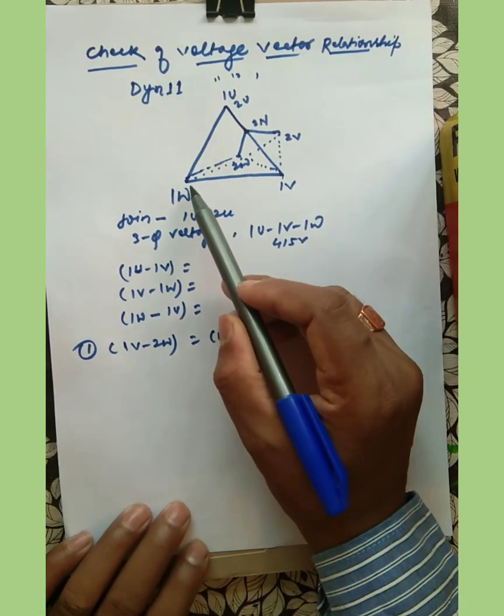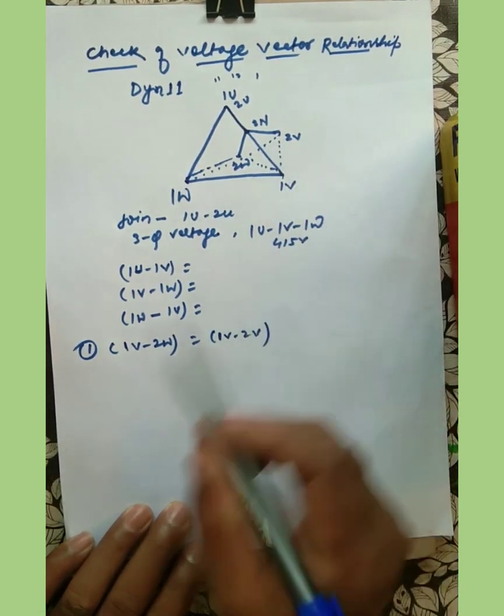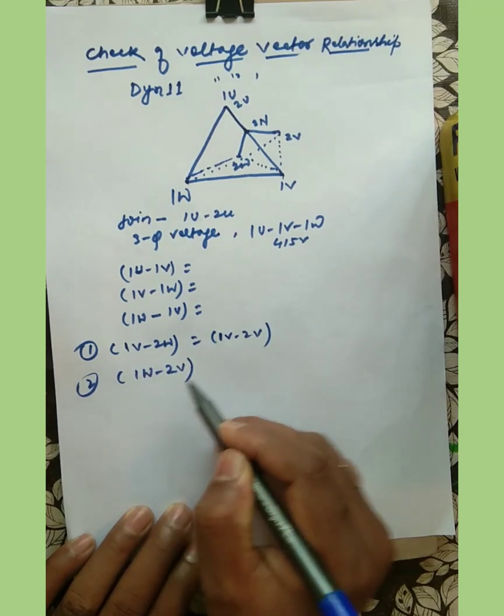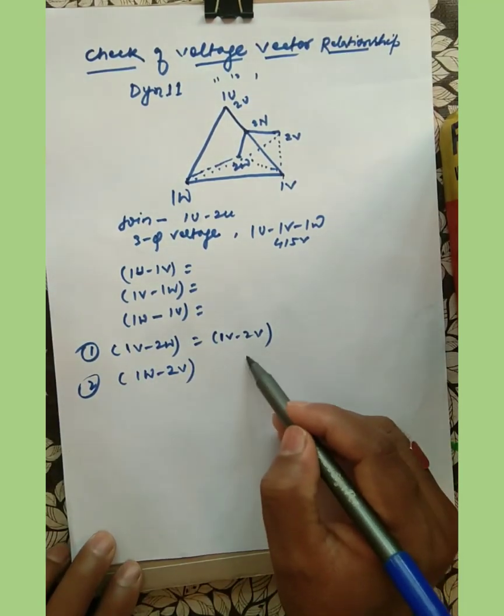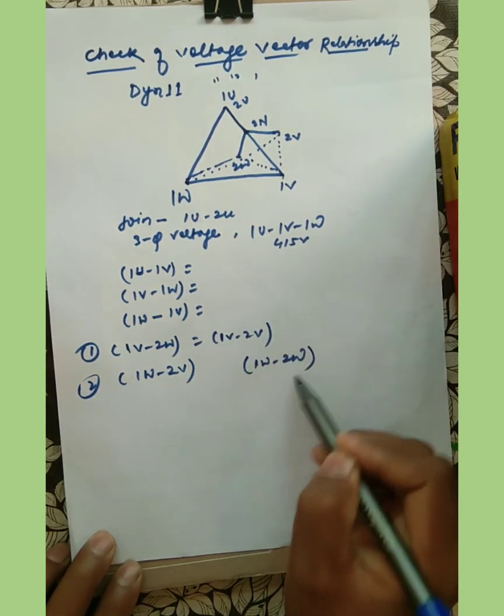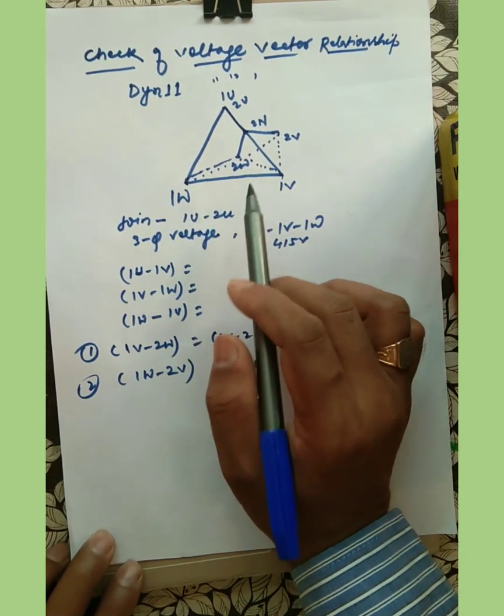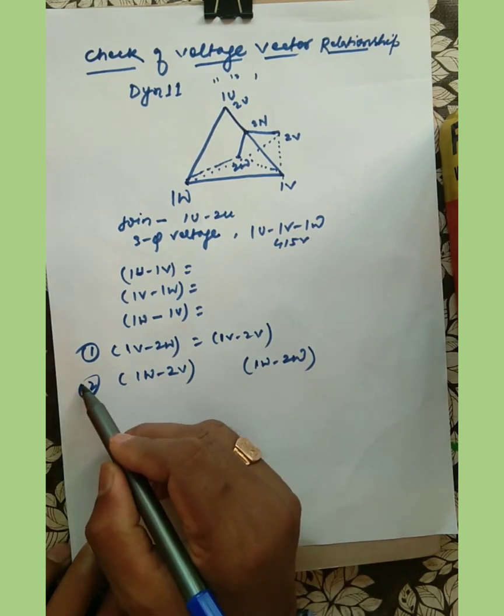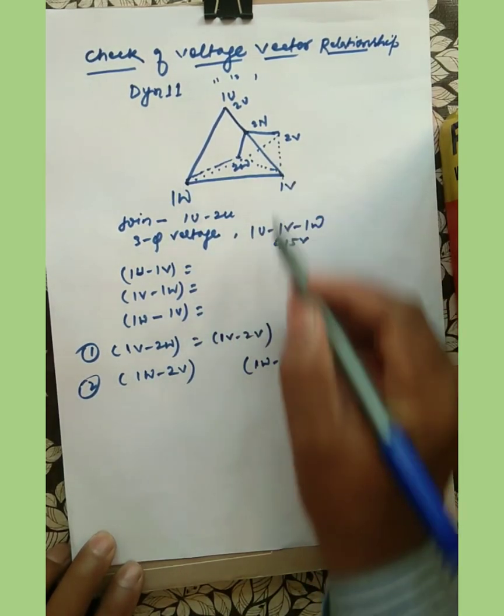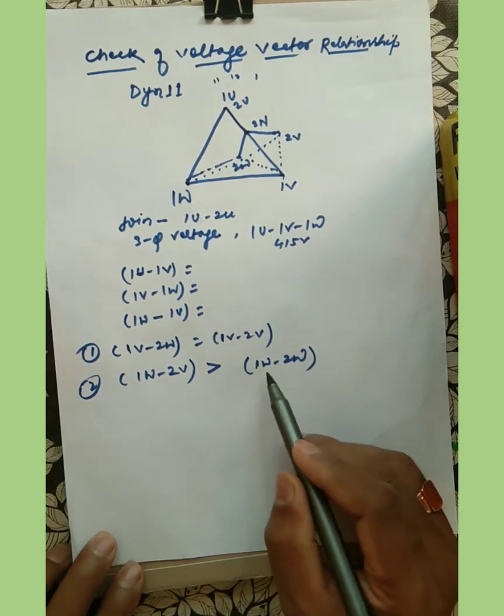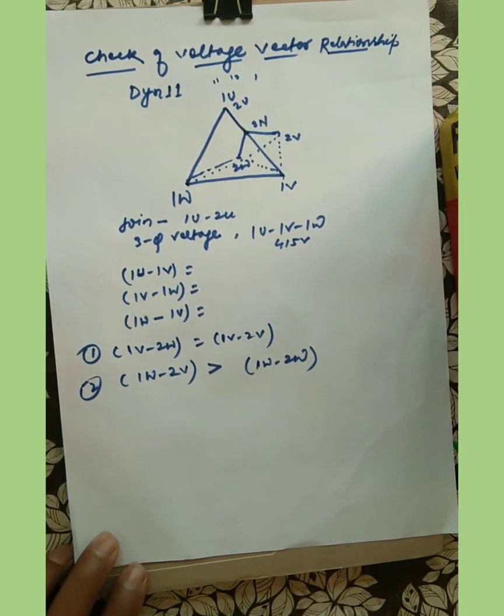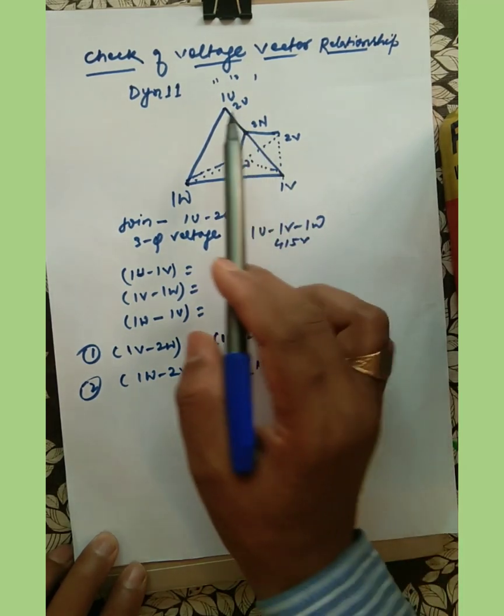The second relationship is that we measure the voltage between 1W and 2V, and between 1W and 2W. The condition is that the magnitude of 1W-2V will always be greater than 1W-2W. That is the second relation.